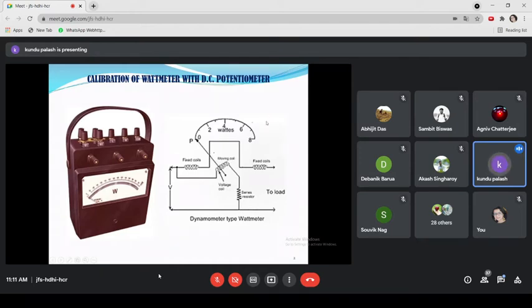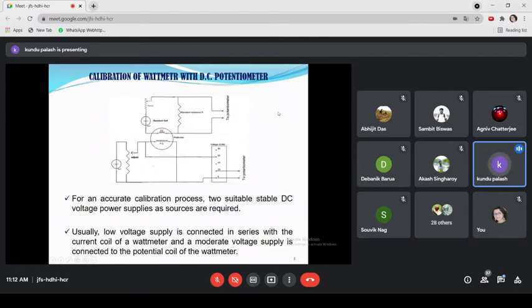Now, what is calibration? The deflections or the readings of the wattmeter must be compared with a reference instrument, following the comparison method. So two wattmeters may be used. One is called a test wattmeter, another is a standard wattmeter which has zero error. Otherwise, here the calibration is done with the help of the DC potentiometer, and this is the calibration circuit.